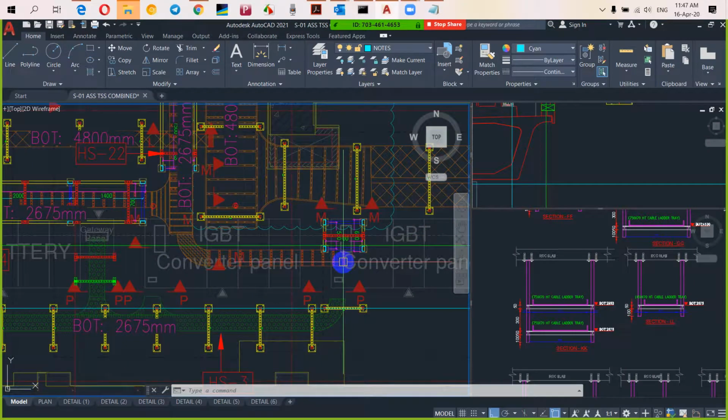Actually, Jamil, one problem is there. On the remaining converter panels, there will be fans on the top, and there will be continuous heat generation. In such a case, I think the cable trays and these cables will get heated up. That's why in the drawing which you have shared, we have diverted the cable trays a bit outside. Okay, so we cannot put the cable tray directly on the top, so we have to route it another way, right? Yes, I will find a way. Please, let me just take some notes.